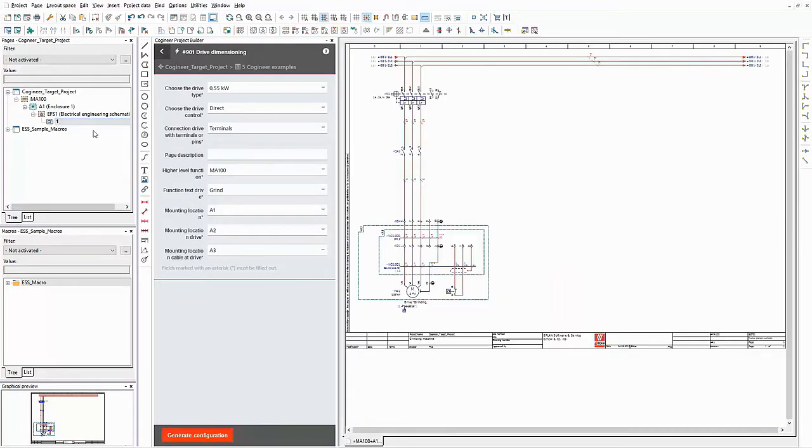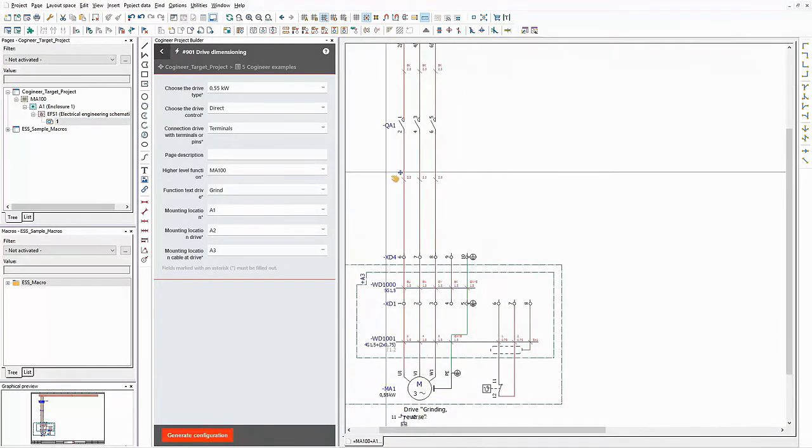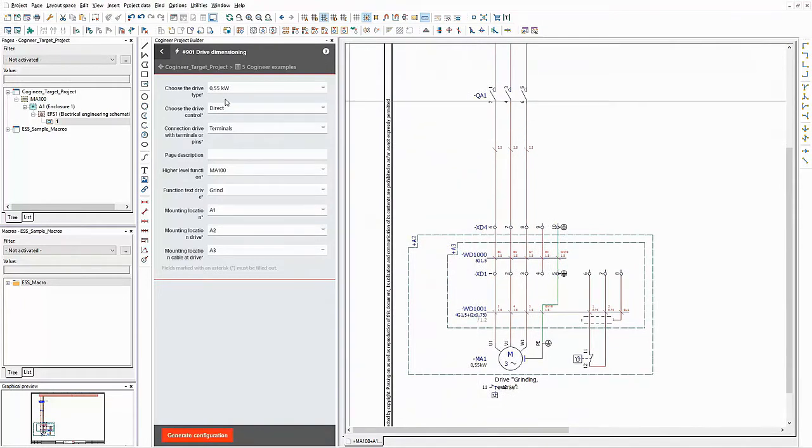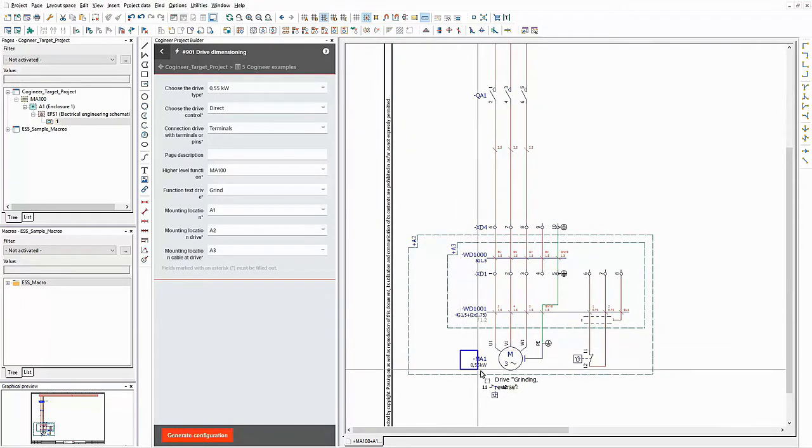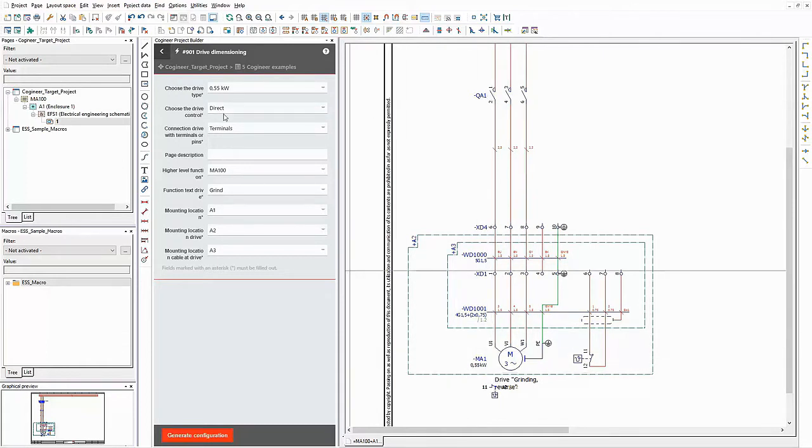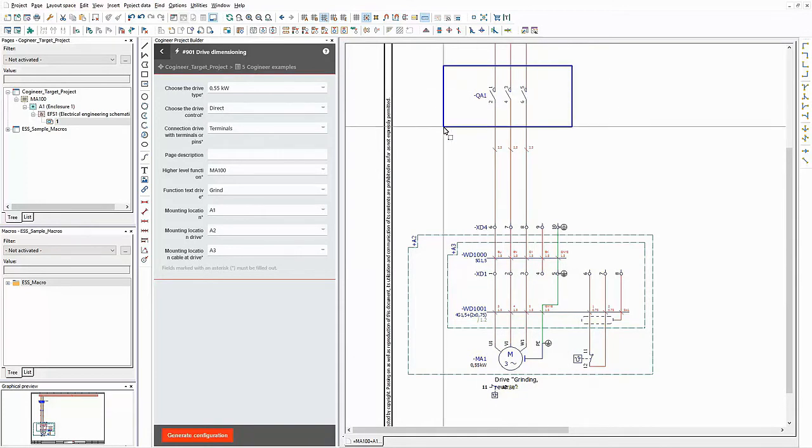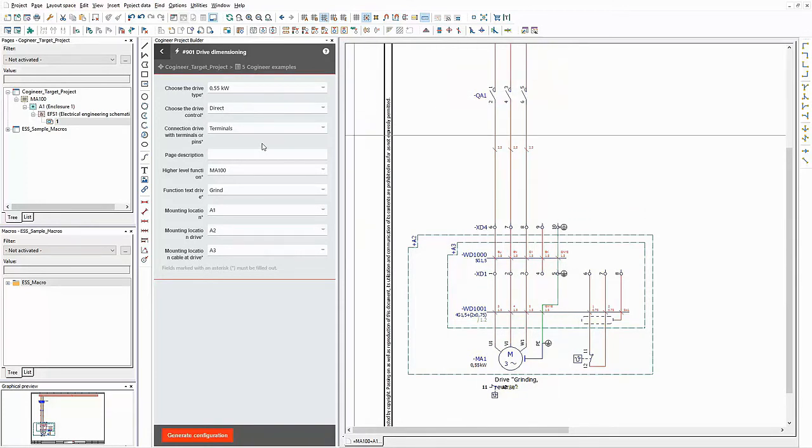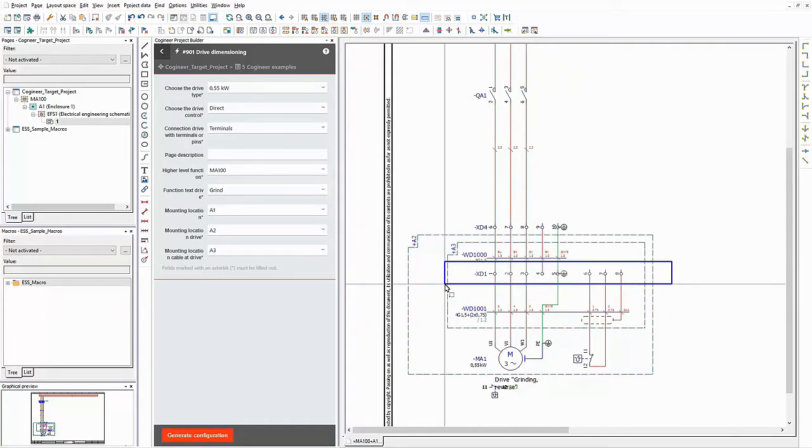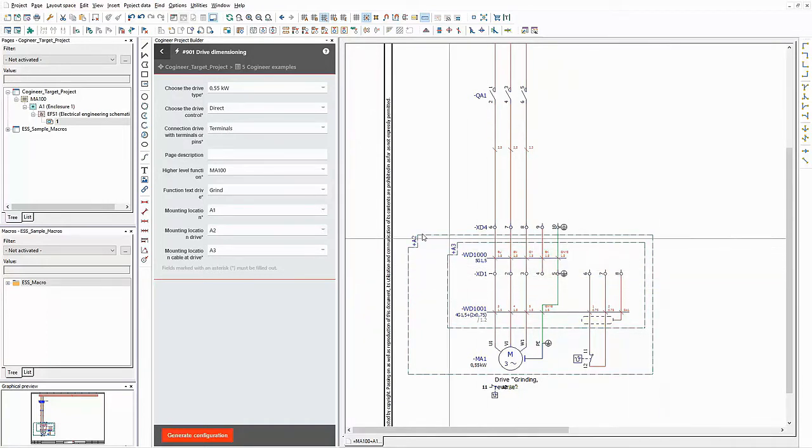Now let's have a look at the drive itself and where we can find the selected options. The basic version has 0.55 kilowatts. You can see this value here. It has a direct drive control without the possibility to switch the rotation direction. This is the according part in the schematic. The drive will be connected to the machine via terminals. They are displayed here.